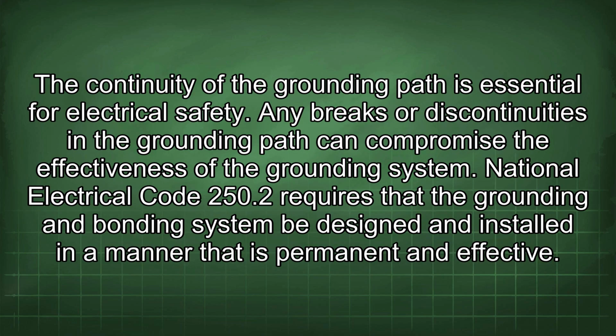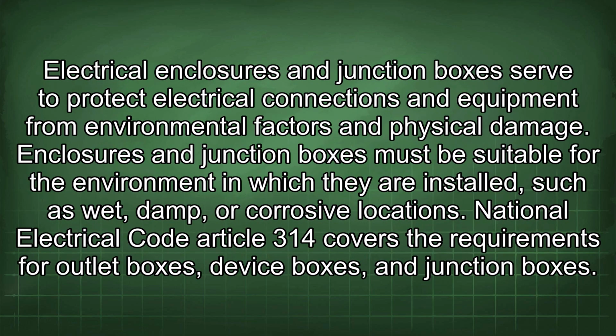250.122. The continuity of the grounding path is essential for electrical safety. Any breaks or discontinuities in the grounding path can compromise the effectiveness of the grounding system. National Electrical Code 250.2 requires that the grounding and bonding system be designed and installed in a manner that is permanent and effective.